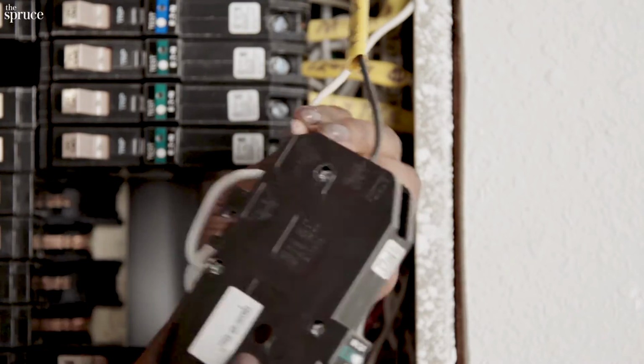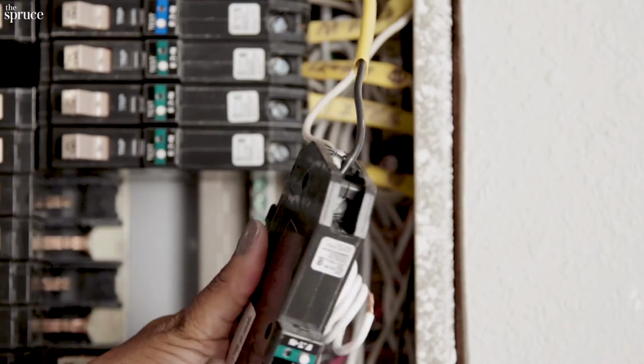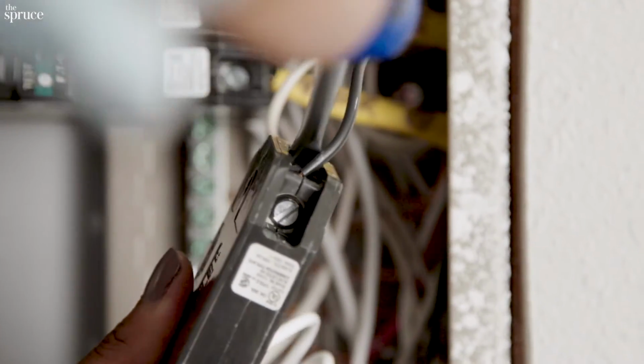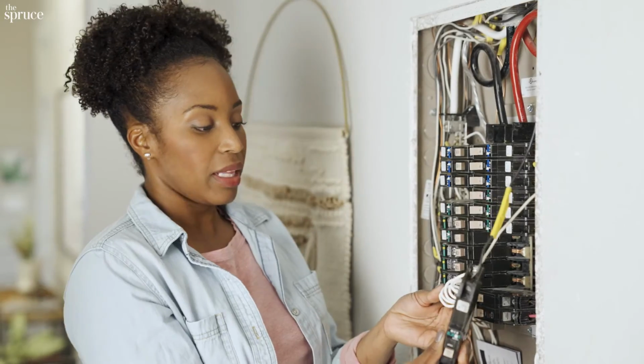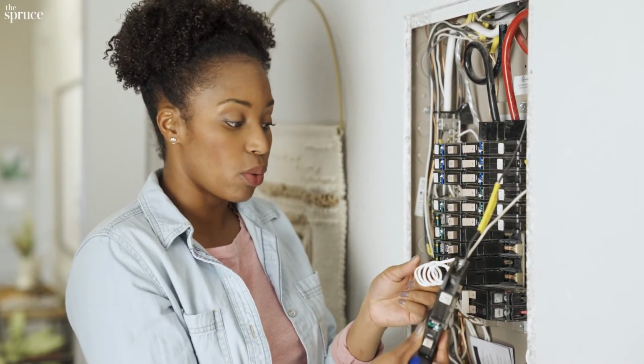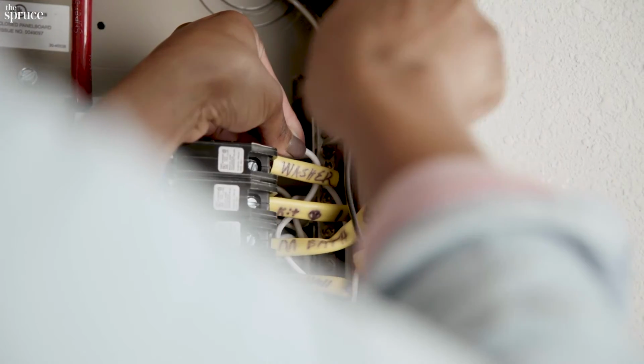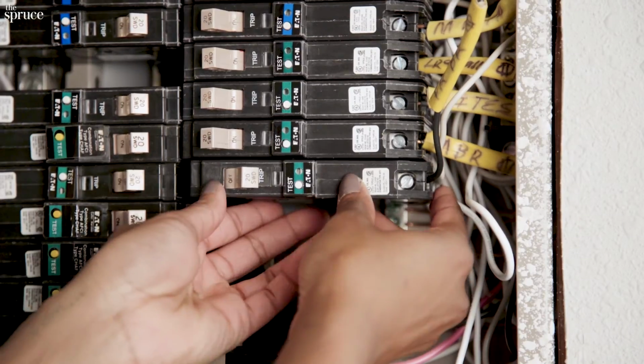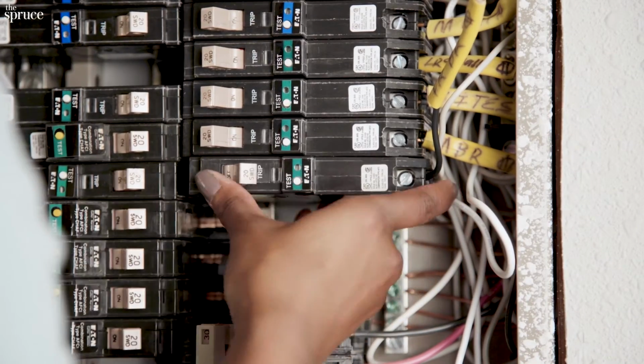Next, I'll attach my neutral wire and then tighten it with the screw. And the last thing I need to do is take this neutral wire and screw it into the neutral bus bar. Perfect. Now it's time to snap the breaker into the bus bar.